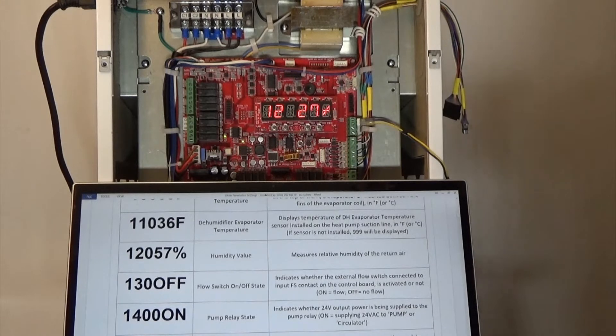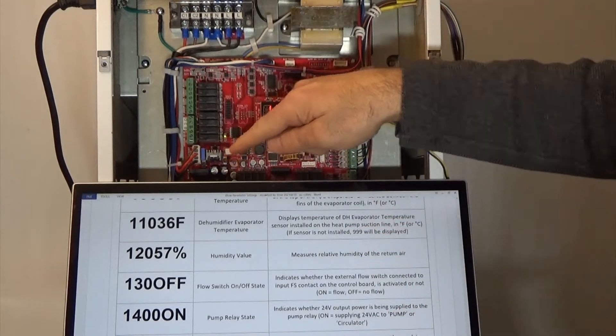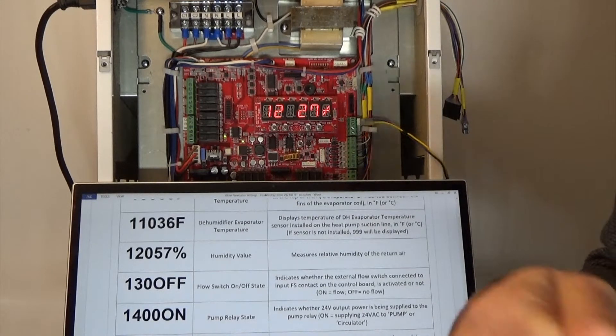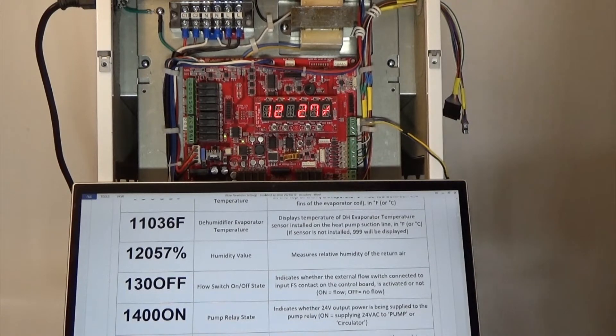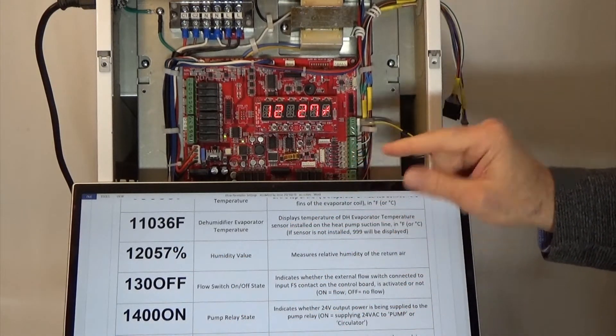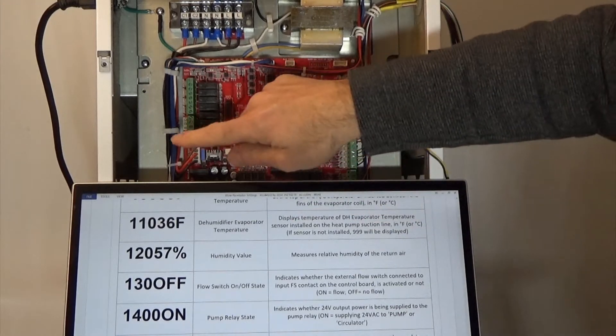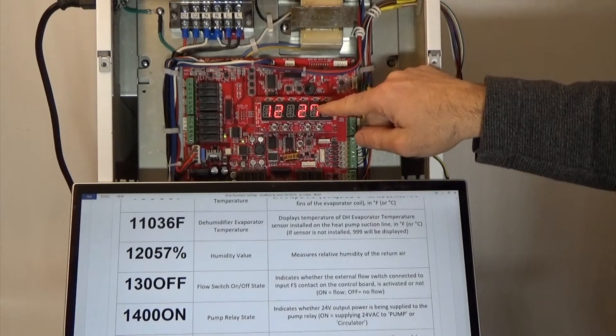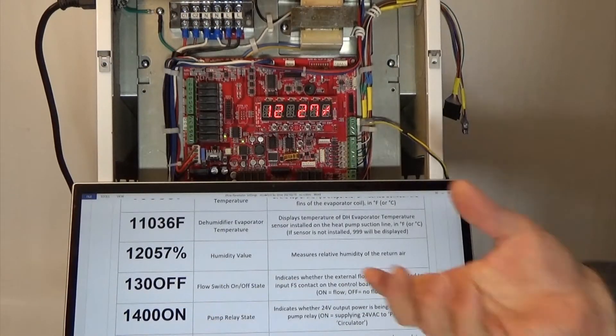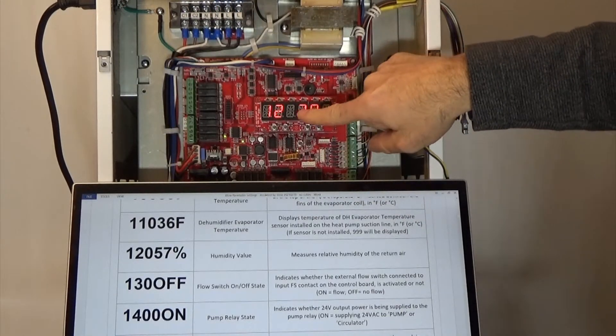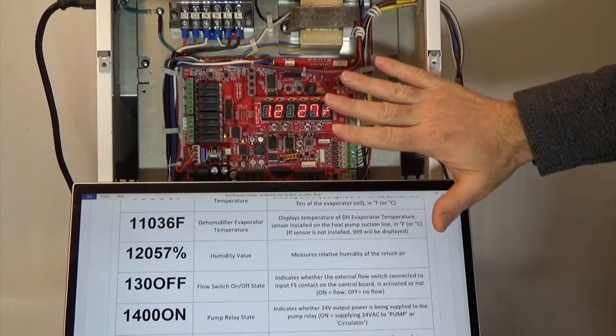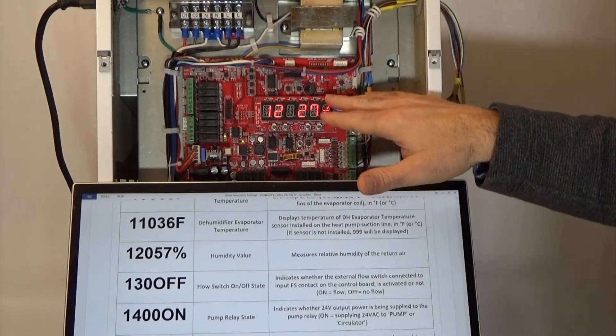Parameter number twelve is the humidity value. We have a humidity sensor that is standard on all Wi-Fi and zoning models — it does not come with the base model, but you can order it as an optional accessory. It measures the humidity of the return air. If the value it reads is below the set point, it will send 24 volts out on the humidifier contact to bring your humidifier on during a heating call. We set this in the general parameters. The info mode is just reading the values — you cannot set or adjust anything in info mode, only read the feedback.